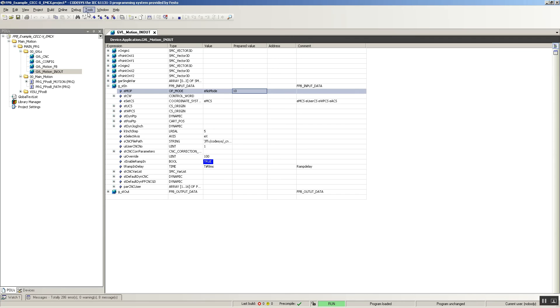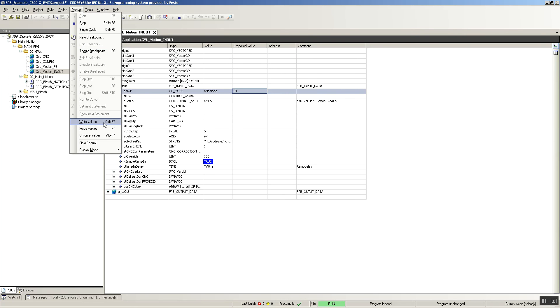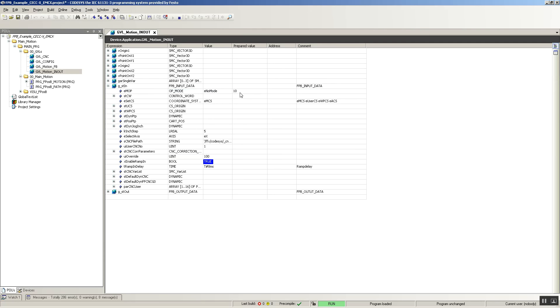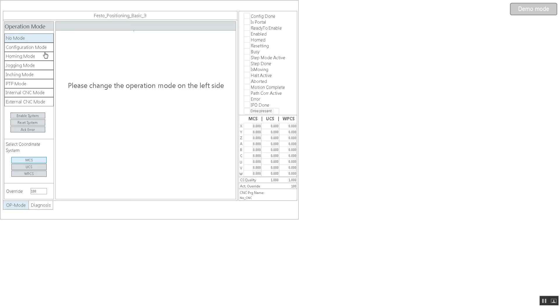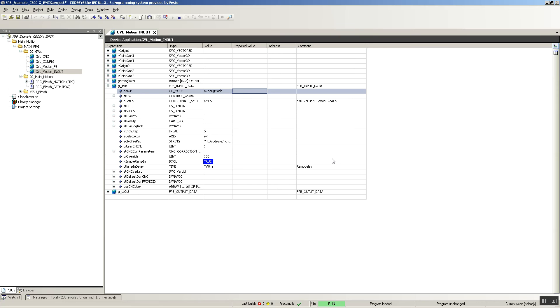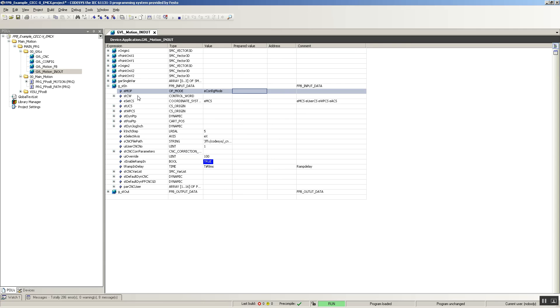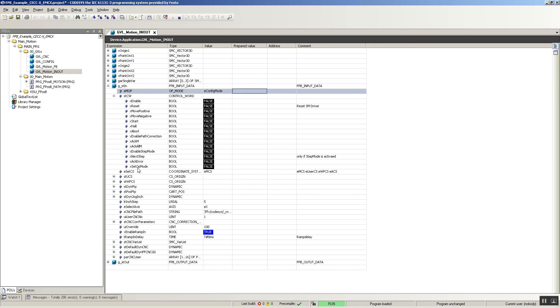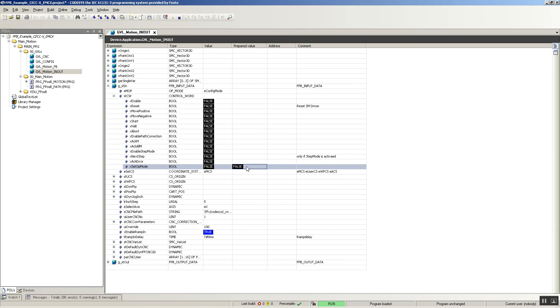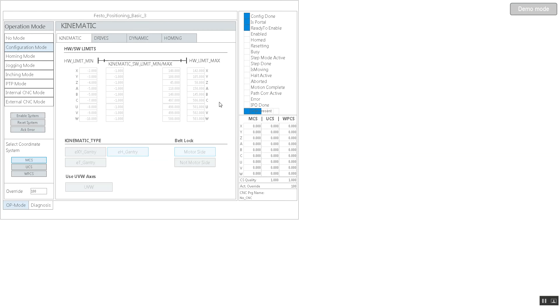So I'm going to do a 10. I'm going to use the shortcut Control F7 to write that value. Before writing that value, let's see the visualization — it's no mode, and the config is not done. I write the value and it's in config mode right now. After doing that, I have to set the operation mode using this bit over here. I have to set this bit to true, write it to true and then false, and the operation mode changes to configuration mode.